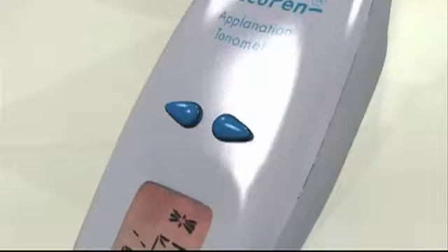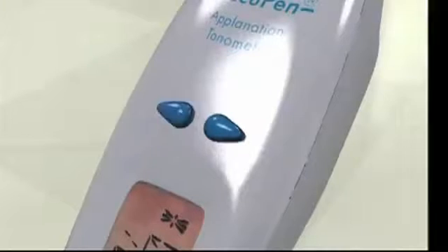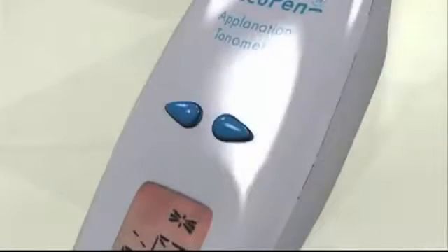If you have taken multiple measurements, an asterisk next to one of the numbers will indicate the furthest from the average. To delete individual measurements, hold down one of the arrow buttons for about 3 seconds. The unit will chirp, indicating the measurement has been deleted. After deleting one measurement, the AccuPen Vet will automatically update the average IOP. To clear the AccuPen Vet completely, hold down both arrow buttons for about 3 seconds. The unit will chirp, indicating the measurements have been deleted.